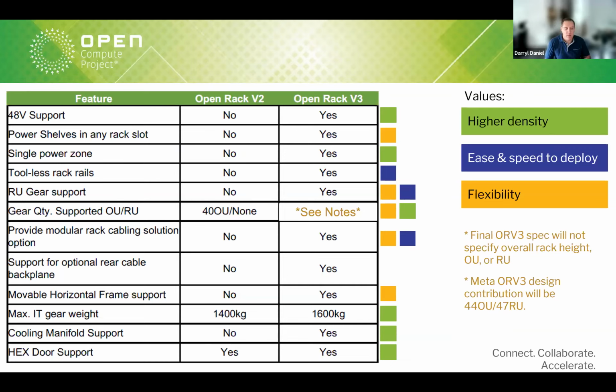We're also going to be providing support for an optional rear cabling backplane for those who might need it - that's new to V3. We also have a movable cross brace in the V3 design. In V2, this was a welded-in member, so you couldn't move it around within the rack, which limited the actual configuration of IT gear - you had to go around that. In the V3 design, that cross member is movable within a certain range, giving you more flexibility in how you stack your IT gear within the rack.